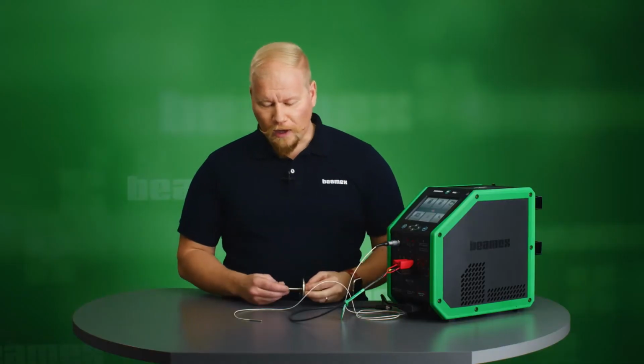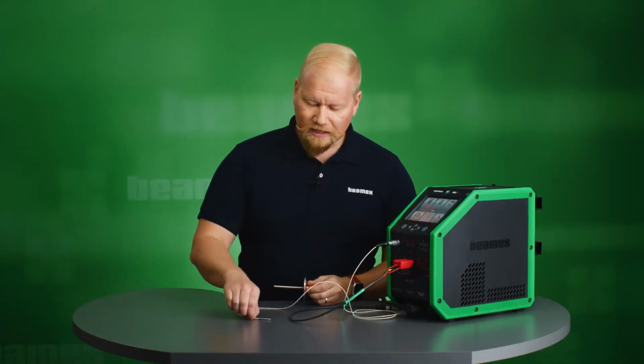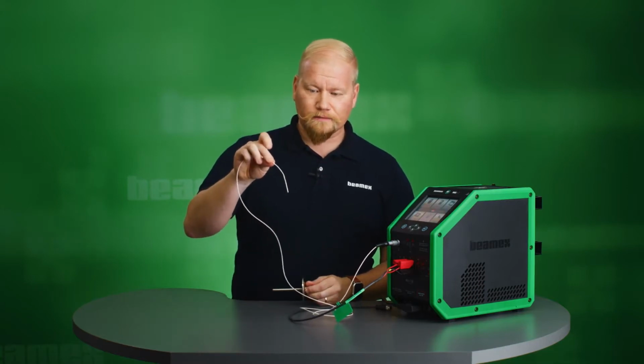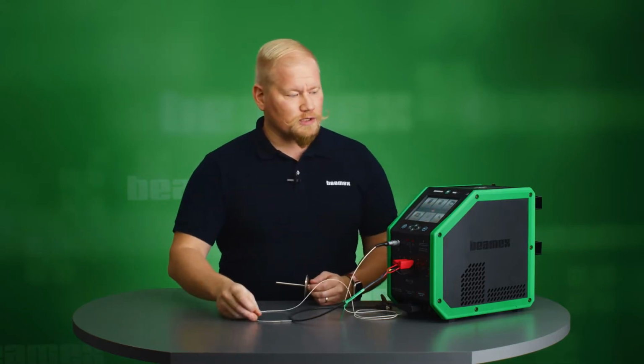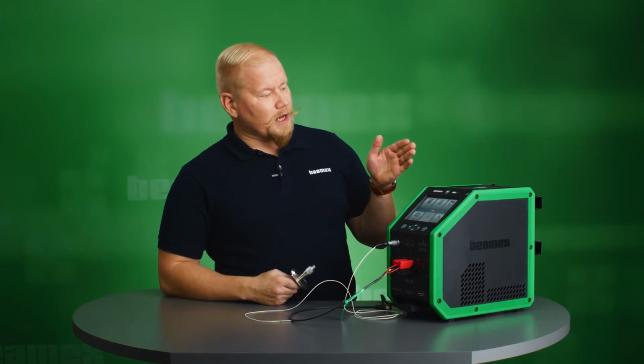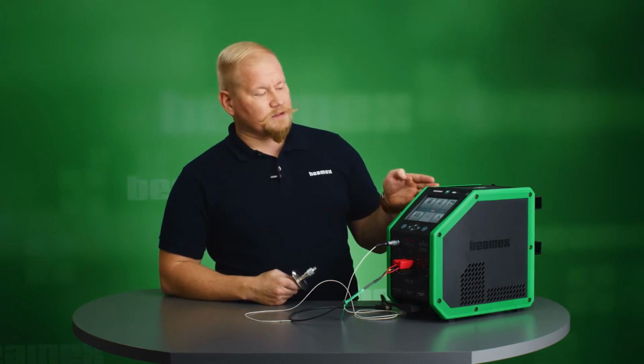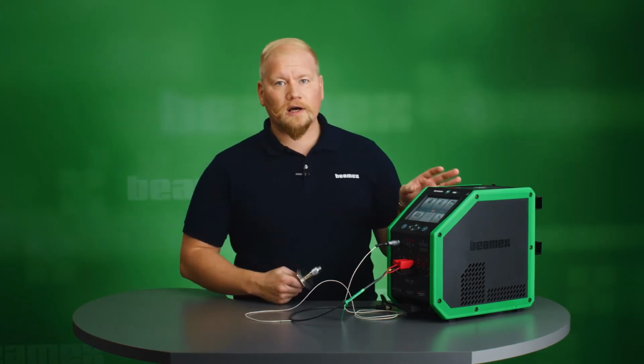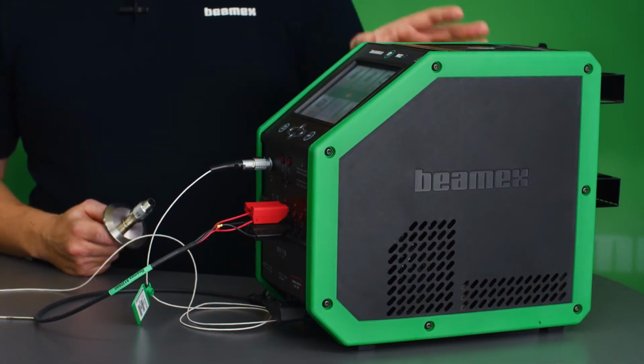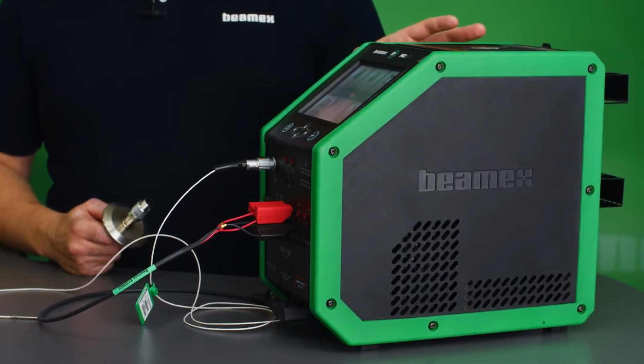I'll show you how to calibrate this short sanitary sensor. To do so, I will also be using a dedicated short reference sensor. And for the heat source, I will be using the MC6-T 150. This is a dry block that has a range of -30 to 150 degrees Celsius.